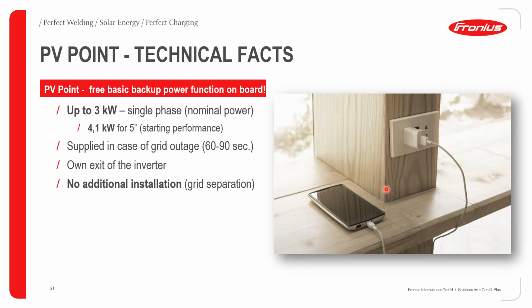Just to give you some technical facts of the PV point, the PV point can give you a maximum of 3 kilowatts output, single phase, okay? It doesn't matter which GEN24 Plus inverter you purchase, it will all give you an output of 3 kilowatts in emergency mode, which is backup mode, which will be single phase. However, we can give you an output of up to 4.1 kilowatts for around about 5 seconds. And this is good if you want to start up any loads, for example, such as a motor that maybe has a very high startup current.